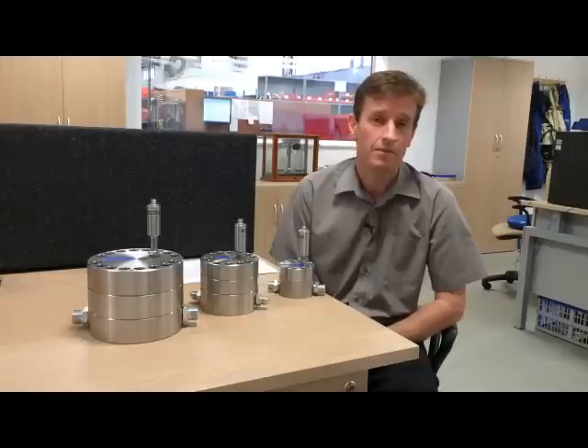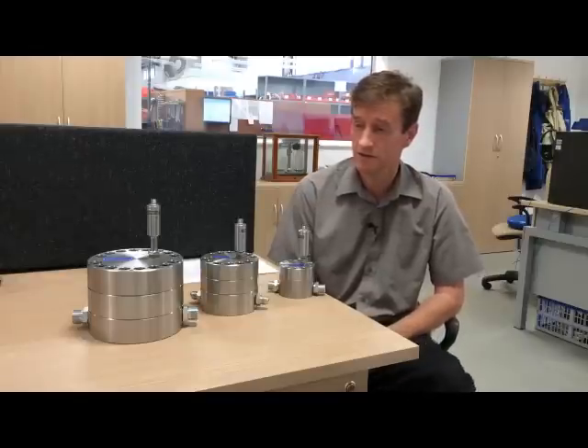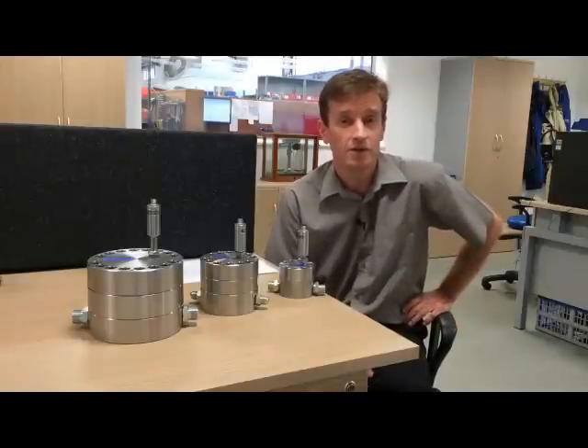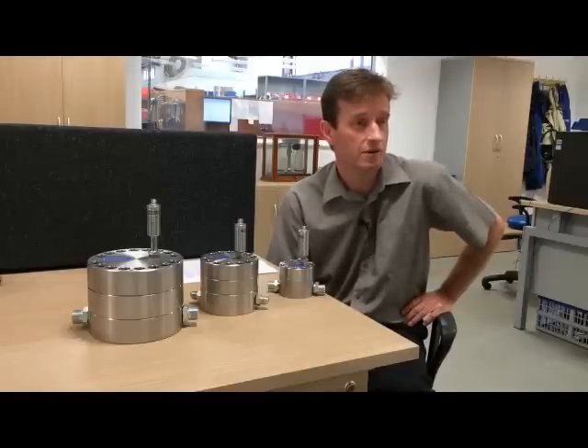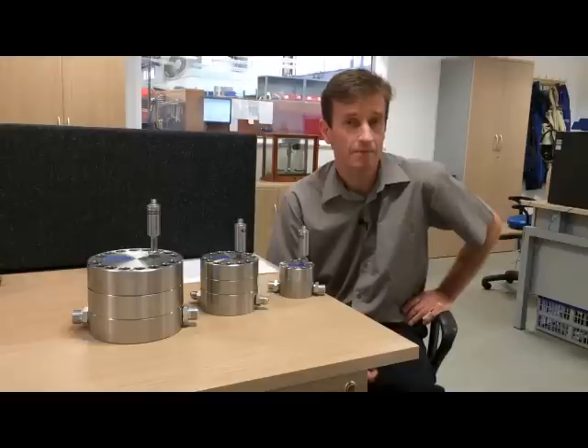The CAN one, well that ties in very well with WebTec's range of meters, HPM type meters, and they'll read out some data loggers. Yes, it'll directly connect to those meters and be auto-sensing, so it'll set up the meter with the appropriate sensor or flow meter calibration details. The customer doesn't have to worry about anything. It's just plug and play and away they go. There's no setting K factors or setting calibration data.